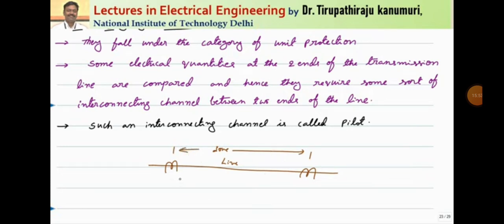We can either compare the currents on the secondary side or we can compare the voltages. These electrical quantities are compared at both ends and are used for making decisions. Such an interconnecting channel — meaning the channel connecting these two quantities — is called the pilot. That is why it is called pilot protection.